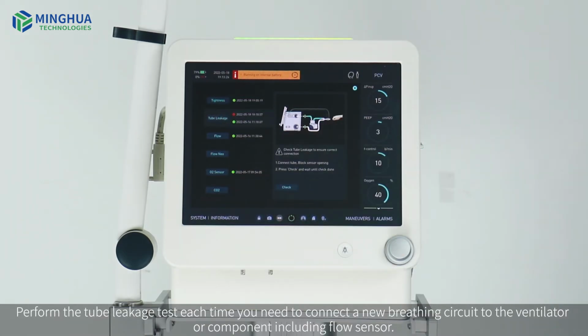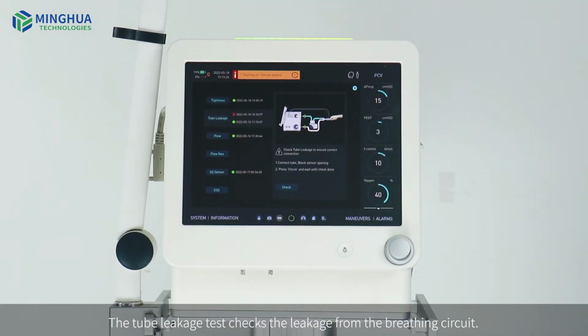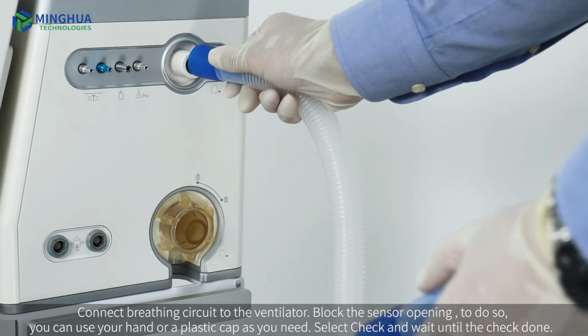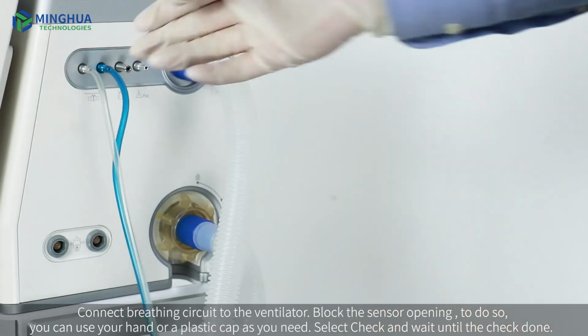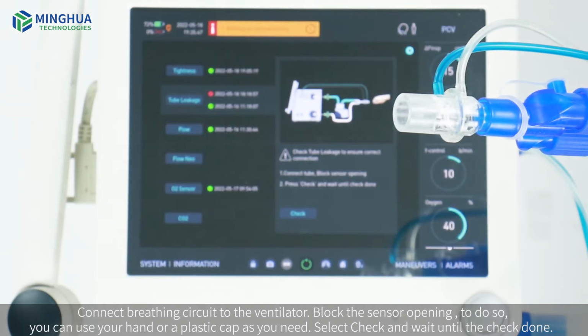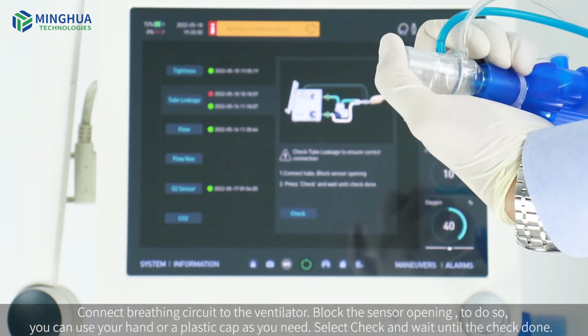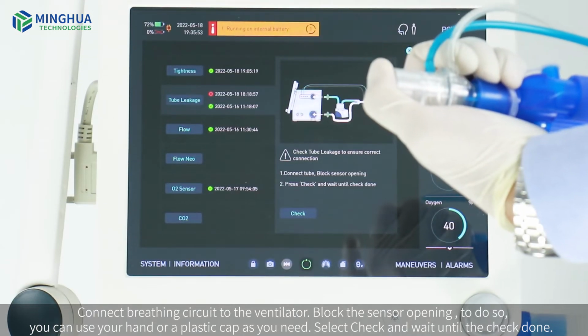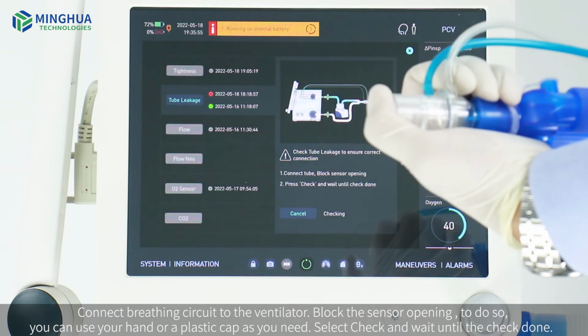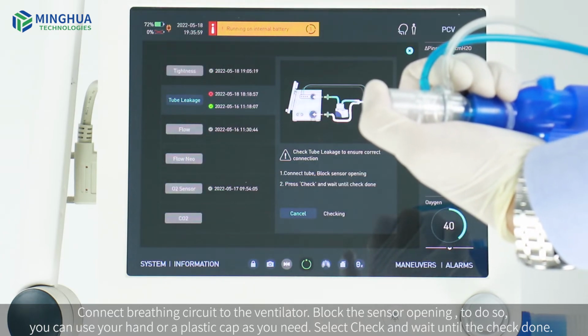Perform the tube leakage test each time you need to connect the new breathing circuit to the ventilator or component including flow sensor. The tube leakage test checks the leakage from the breathing circuit. To perform the tube leakage test, follow the operational instructions from the ventilator. Connect the breathing circuit to the ventilator. Block the sensor opening. To do so, you can use your hand or a plastic cap as you need. Select Check and wait until the check done.